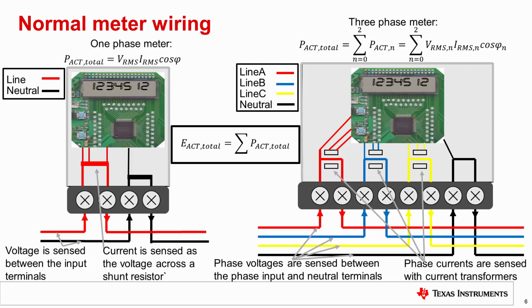The figure on the right shows a three-phase meter. This is similar to three one-phase meters, with the voltage being measured between a particular phase's line and the neutral, and the current being measured between the corresponding phase's line in and line out terminals. To calculate the total active power for a three-phase meter, the active power of each individual phase is added together. By accumulating the active power, you calculate the active energy, which is the quantity that utility customers are billed by.